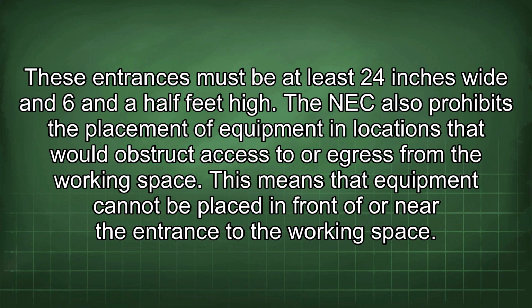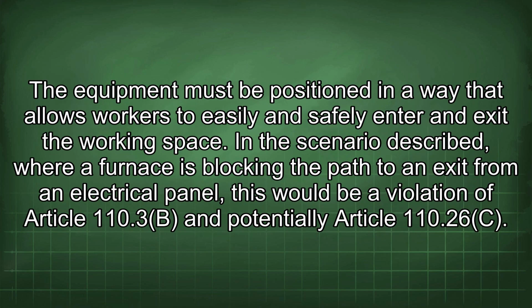The NEC also prohibits the placement of equipment in locations that would obstruct access to or egress from the working space. This means that equipment cannot be placed in front of or near the entrance to the working space. The equipment must be positioned in a way that allows workers to easily and safely enter and exit the working space. In the scenario described, where a furnace is blocking the path to an exit from an electrical panel, this would be a violation of Article 110.3(B) and potentially Article 110.26(C).